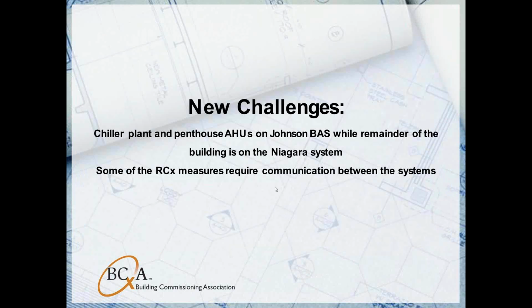So with the chiller plant controls upgrade, we unintentionally added some new challenges to this project. Now that the chiller plant and the penthouse air handlers are on the Johnson BAS, the remainder of the building remains on the Niagara system, which poses a problem for some of our retro commissioning measures that we recommended, most importantly, static pressure reset. We can't do static pressure reset now because we don't have communication between the VAV boxes and the air handlers in the penthouse.